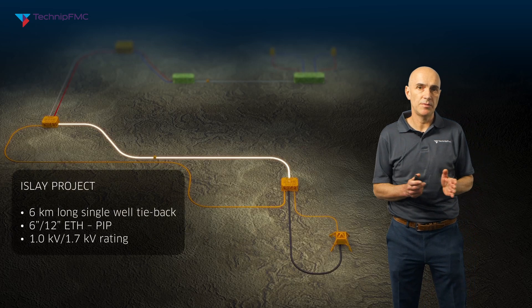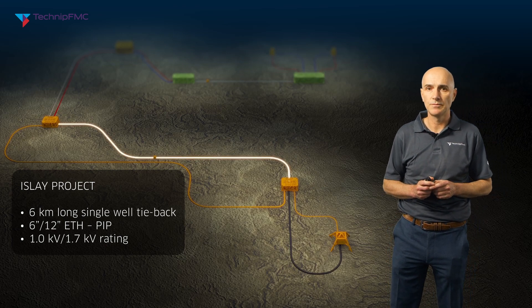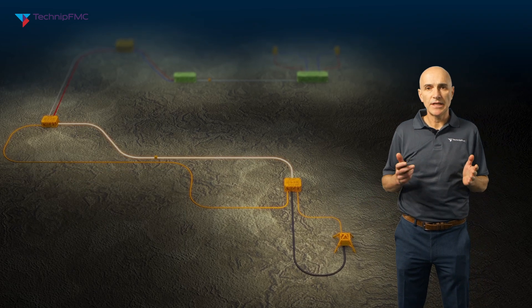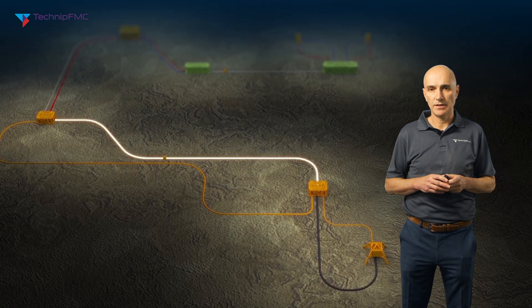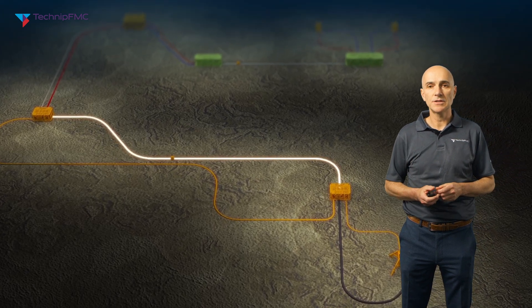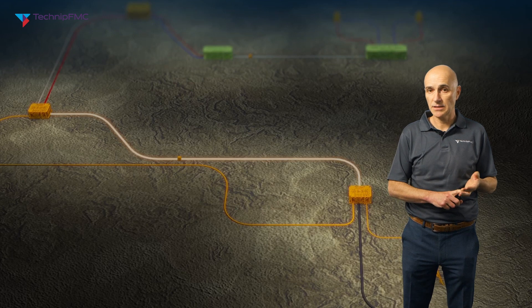Technip FMC has installed two ETH pipe in pipe systems to date. The first was for the Islay project in the UK sector of the North Sea, installed back in 2011. This was a small ETH pipe in pipe: a six inch inner pipe inside a 12 inch outer pipe, six kilometres long, installed in just over 100 metres water depth, with cables rated to 1 kilovolt phase voltage. The system was essentially installed as a technology demonstrator — active heating was not required for Islay field production, but it allowed the operator to confirm the system functioned as intended and provided a reliable and effective means of active heating, tested both at installation and during the early years of production.